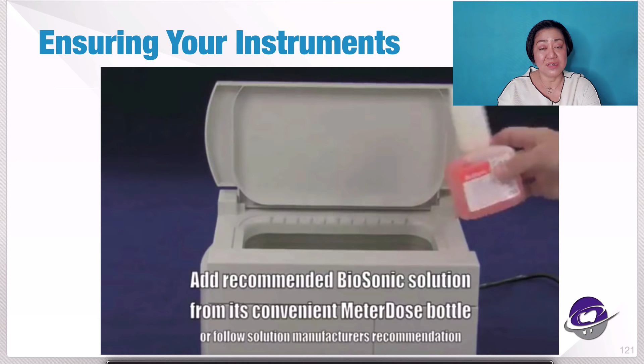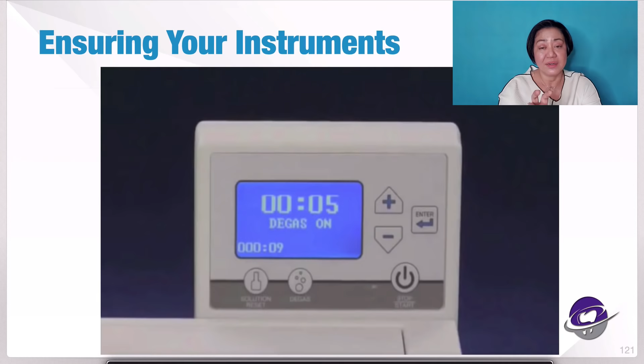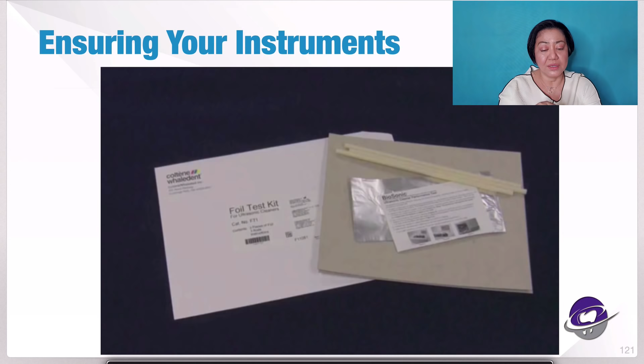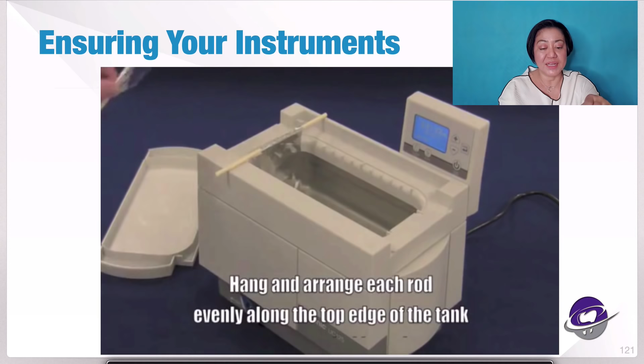And then of course, you have to test or degas it at least once a week, to check if the ultrasonic cleaner is really working well. And that is with the use of a stick, like a barbecue stick, and a Reynolds foil. You wrap the edge of the foil tight on the stick, and you do that with like 3 or 4 sticks, and then allow the ultrasonic cleaner to run, again according to the manufacturer's instructions. So for this, it's 5 minutes. If you remove the foil, it should have this kind of pitted and wrinkled pattern. Otherwise, if it doesn't have it, it's not working well.